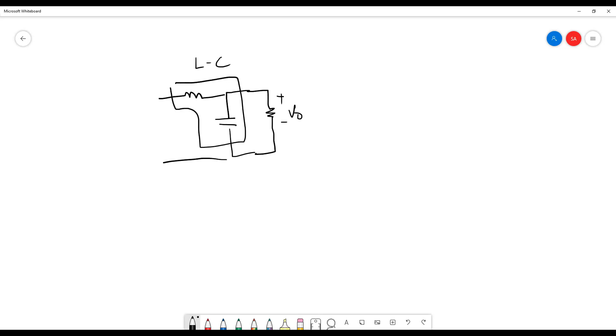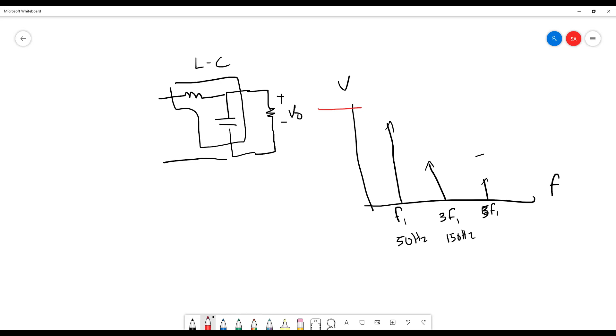In the frequency spectrum, voltage versus frequency, this is your f1, and the nearest is 3 times your f1. If your f1 is 50 Hertz, the frequency of the nearest third harmonic is 150 Hertz, then the 5th harmonic is 5 times f1, and so on. To remove the third and 5th, you need a low pass filter that has a cutoff frequency fc below 150 Hertz. To get this cutoff frequency fc, you need to calculate the values of L and C using this equation.